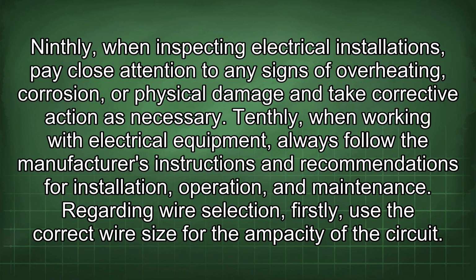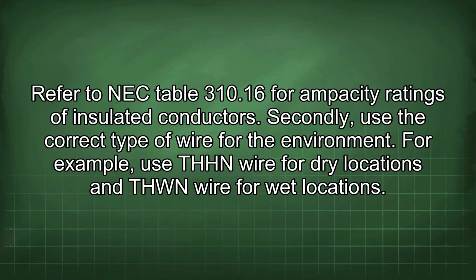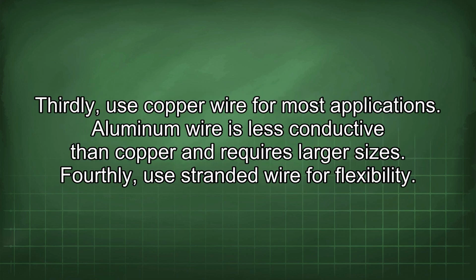Regarding wire selection, firstly, use the correct wire size for the ampacity of the circuit. Refer to NEC Table 310.16 for ampacity ratings of insulated conductors. Secondly, use the correct type of wire for the environment. For example, use THHN wire for dry locations and THWN wire for wet locations. Thirdly, use copper wire for most applications. Aluminum wire is less conductive than copper and requires larger sizes.